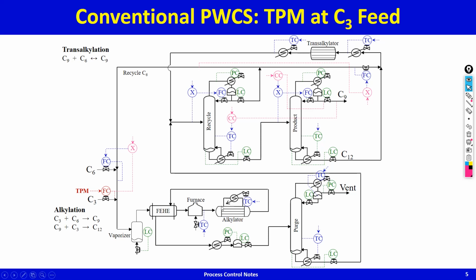So because the inlet condition into the reactor has changed, more reactant is coming in. For the same reaction rate, the hotspot will move down. Hotspot moves down, hotspot temperature will go up a little bit. I don't know how that will behave, but the bottom line is reactor temperature will increase. As reactor temperature increases, you will increase the cooling duty to maintain the hotspot temperature.